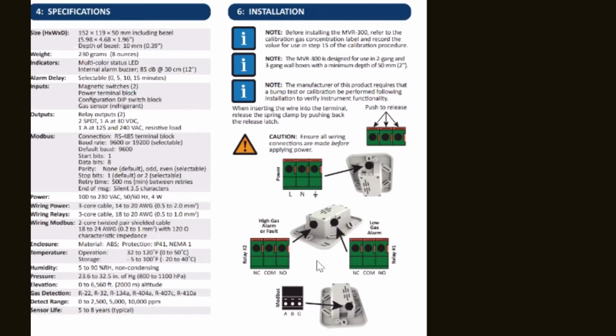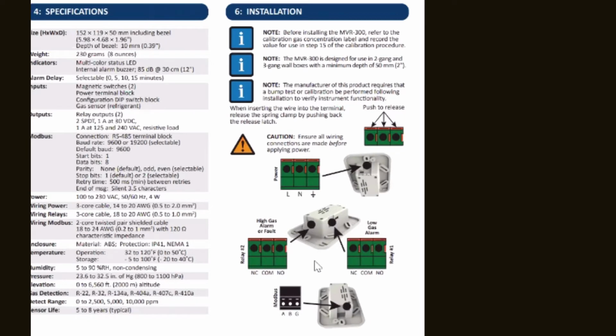Yeah, Ken, so sorry to interrupt you, but the low gas alarm and high gas alarm, our thoughts were to take that low gas alarm, because from my standpoint, if there is any kind of alarm that goes off because of refrigerant gas, we want to know about it, and we were going to tie that into our nurse call system.